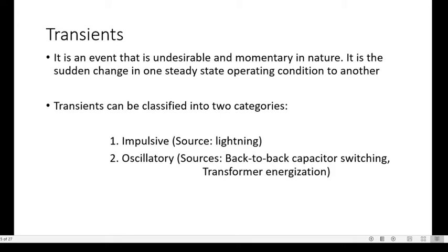On the motors, the transient will make motors run at a higher temperature due to increased I2R losses. Transient degrades the insulation of the motor winding, resulting in burning or fire. It increases the motor losses, hysteresis losses, and its operating temperature.